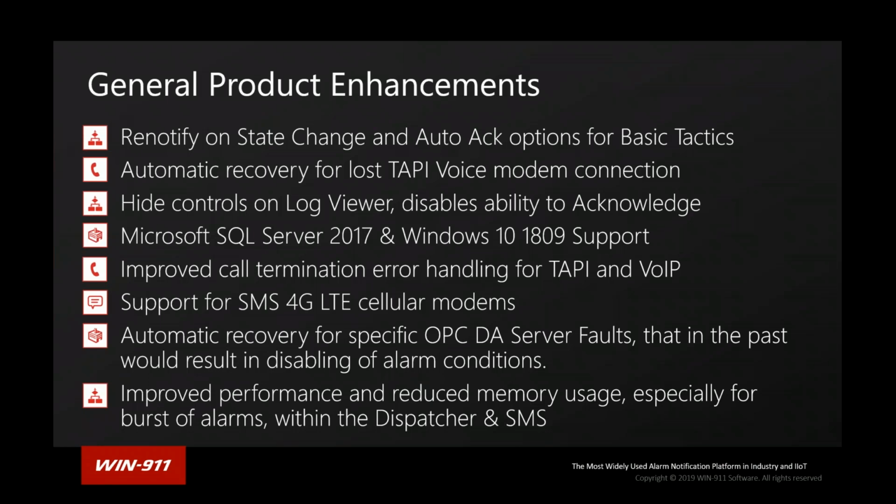However, we have found some faults that are recoverable, and so what we've done is look for these specific faults that we know we can recover from. If we get updated with a bad quality in one of these certain server faults, we will treat it just as if it was a bad quality. We will keep the handle on the item.